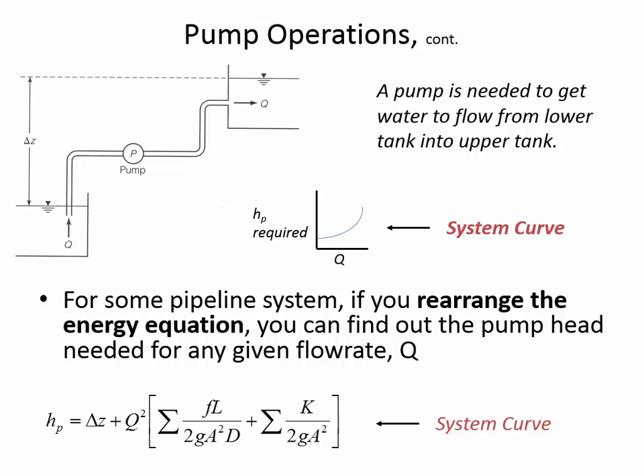So here's the friction loss term. Here's the local loss term, that's due to those bends and the entrance and the exit losses. And it all depends on the flow rate. So this is telling us that at 0 flow rate, how much energy do we have to add to get the water from the lower reservoir to the upper reservoir? If we have a very, very low flow rate, just a trickle, well, at the very least, you have to add enough energy to overcome the delta Z. So if Q is essentially 0, you, as a minimum, have to add enough pump head to overcome the delta Z. But then if you want to have a higher flow rate than that, then you have to add even more pump head.